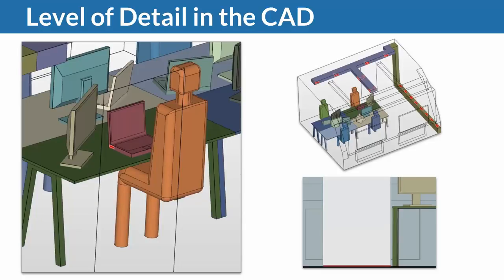Below the door, I also added a very small patch, which will allow for extra blow-by and extra air exchange of the room with the corridor that is outside. You could add this kind of features also below the windows. Otherwise, we would have a room that is completely sealed and completely isolated, perfectly isolated, which is most of the time not the case in real life. There are small openings behind the windows, there are small openings below the door or around the door, which will also influence the overall flow balance inside the office space.